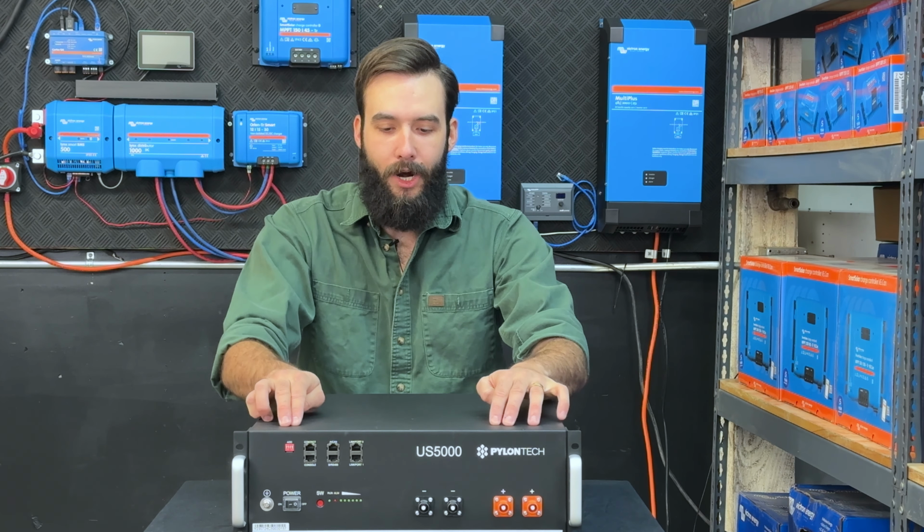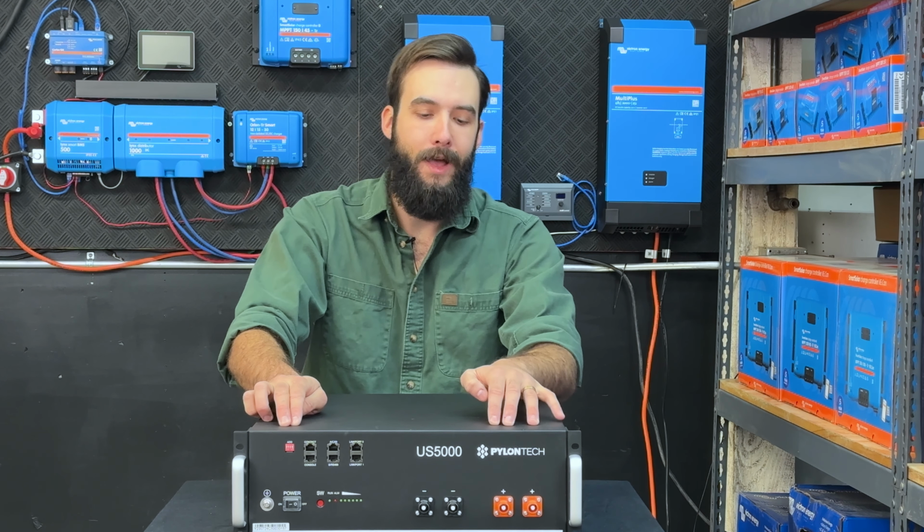The next thing to talk about is the BMS. The BMS, which takes up about this much of the front half of the battery, is the industry standard. Now, BMS is a battery management system. For most BMSs, they're not really managing anything. We see a lot in this market that the BMS effectively acts just as a kill switch. They're to shut operation down if parameters get outside of spec. If we're dealing with voltage imbalances, adverse temperatures, crazy inrushes of current, a BMS is just going to close the gate, turn the battery off, prevent damage.